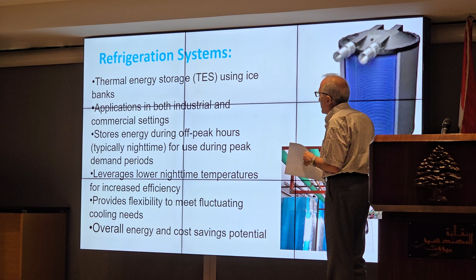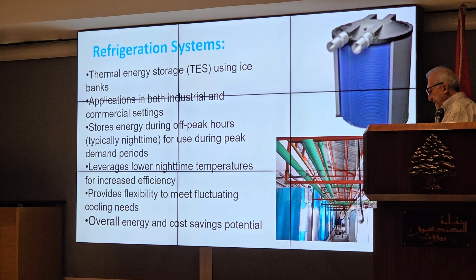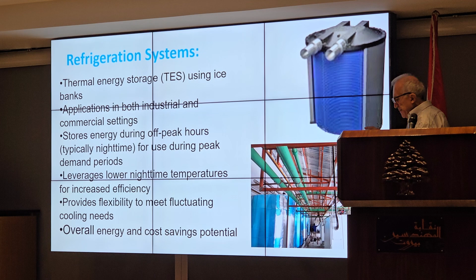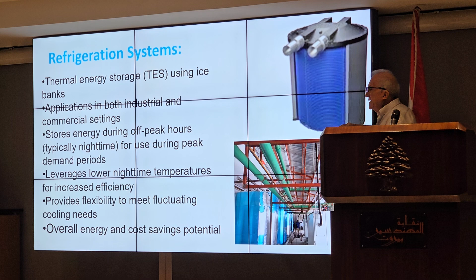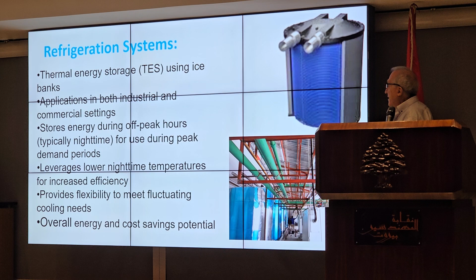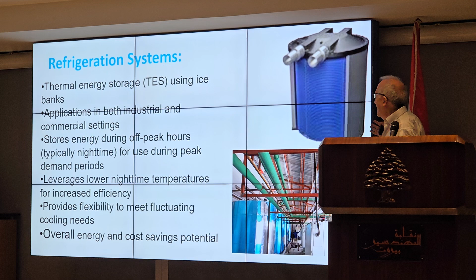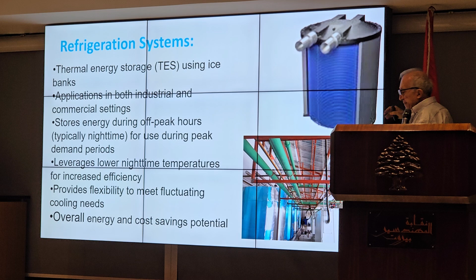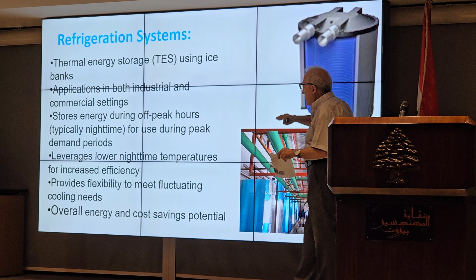Thermal energy storage also in the industrial sector. Thermal energy storage, specifically ice banks like the one shown here, offers a solution for managing energy demand in both industrial and commercial settings. The concept is simple. We store energy during the night, when the electricity tariff is low, and the outside conditions are good for condensing the refrigerant, so you can have higher COP, and they also allow, in general, in the industry to shape the peak load.